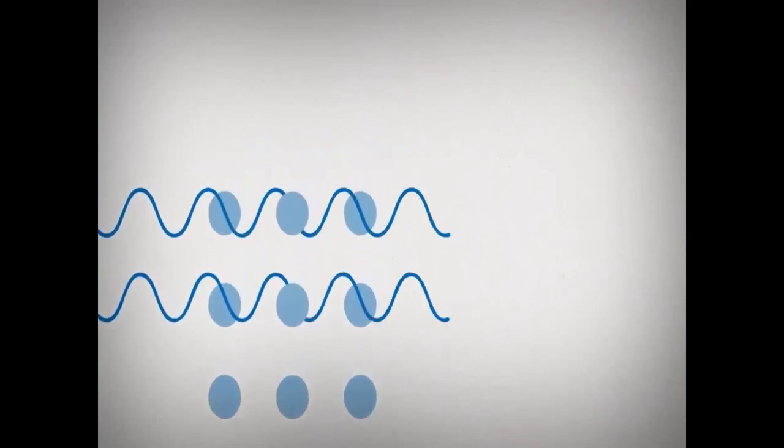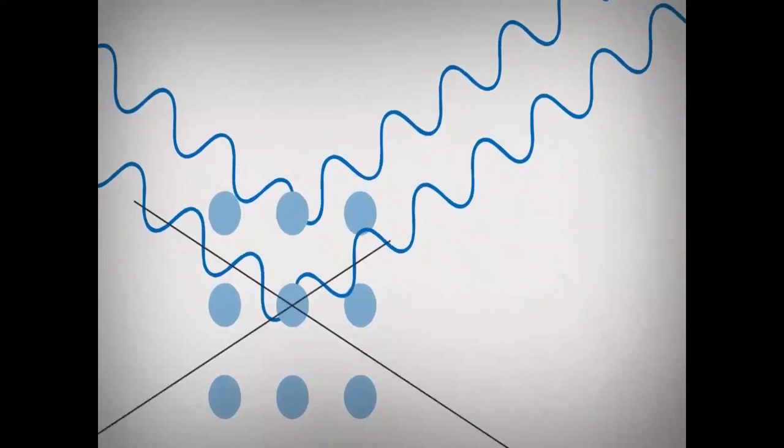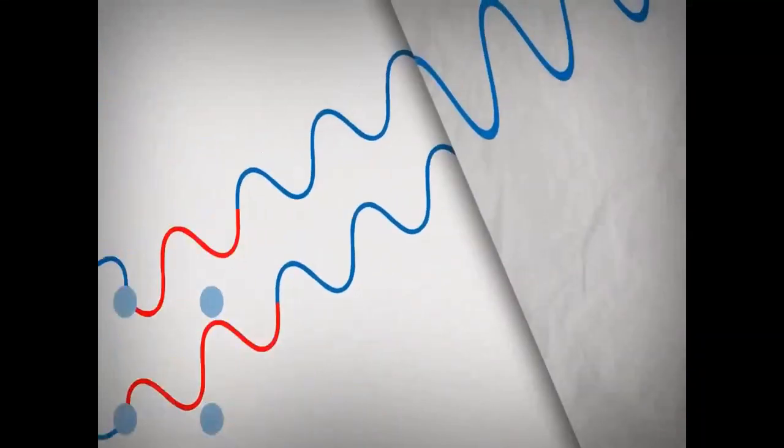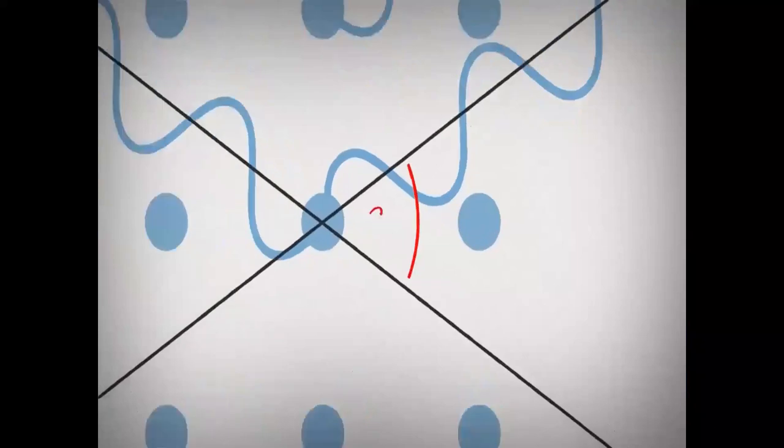In a crystal, the repeating arrangement of atoms form distinct planes separated by well-defined distances. When the atomic planes are exposed to an X-ray beam, X-rays are scattered by the regularly spaced atoms. Strong amplification of the emitted signal occurs at very specific angles where the scattered waves constructively interfere. This effect is called diffraction. The angle between the incident and the scattered beam is called two theta.